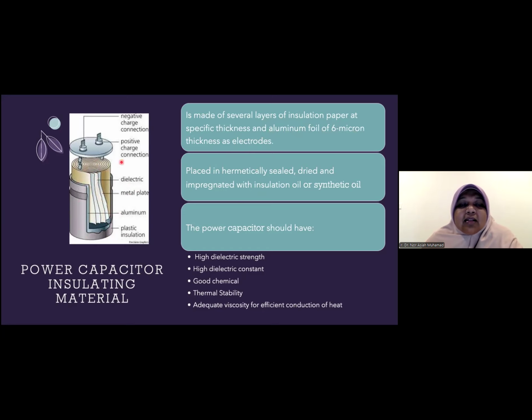It must be hermetically sealed to prevent any oxygen from coming in, because our atmosphere has water content, and we don't want it to enter inside, as it will degrade the insulation as well as the conductor. So the power capacitor should have high dielectric strength, high dielectric constant, good chemical and thermal stability, and adequate viscosity for efficient conduction of heat. Okay, there are some power capacitors where the paper and the aluminum are immersed in oil, the oil-based power capacitor.